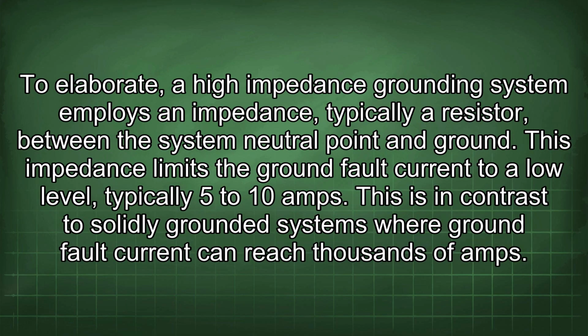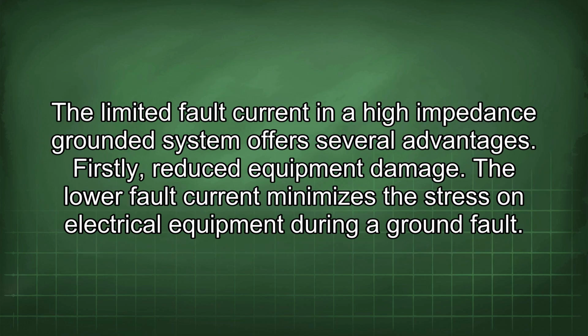To elaborate, a high-impedance grounding system employs an impedance, typically a resistor, between the system neutral point and ground. This impedance limits the ground fault current to a low level, typically 5 to 10 amps. This is in contrast to solidly grounded systems where ground fault current can reach thousands of amps. The limited fault current in a high-impedance grounded system offers several advantages.